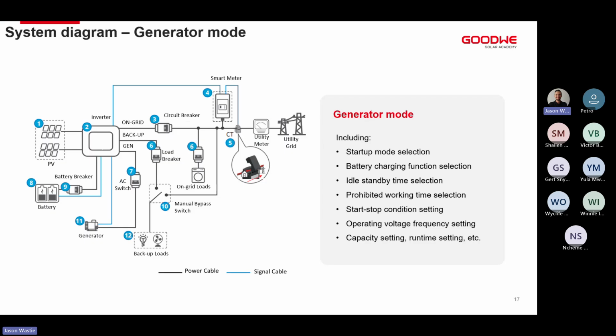We'll have a look at some of these system diagrams. The first one is the generator. When it comes to the generator, we have 3 different ways we can use the physical generator port, or dedicated generator port. On the inverter itself, we have 2 5-amp dry-contact relays. The first relay we use for start-stop functionality on a generator. So if your generator has a Deep Sea controller or any sort of smart controller that allows for start-stop functionality through a contactor or a relay, we can use our dry contact relay to start the generator up when we require it to.